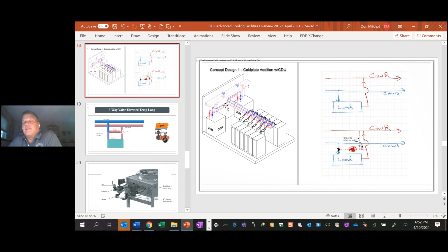Well, but I appreciate that. What happened was we had this discussion, just doing the what-ifs, and we said, do you really need to put in a CDU? In many cases these IT racks may have a CDU built inside, there may be a heat exchanger. You're not going to want to run facility water through a cold plate, cold plates aren't designed for the pressures or water quality of facility water, but you may want to take facility water and run that through the CDU that feeds your cold plate.